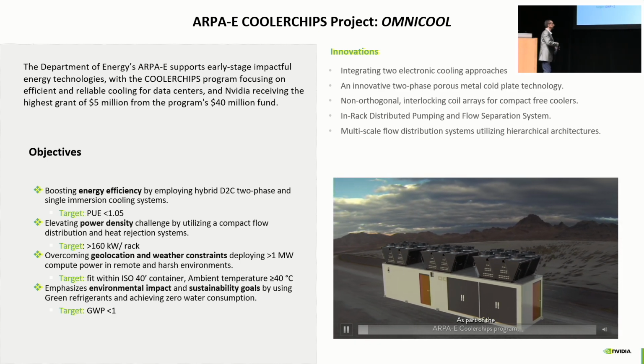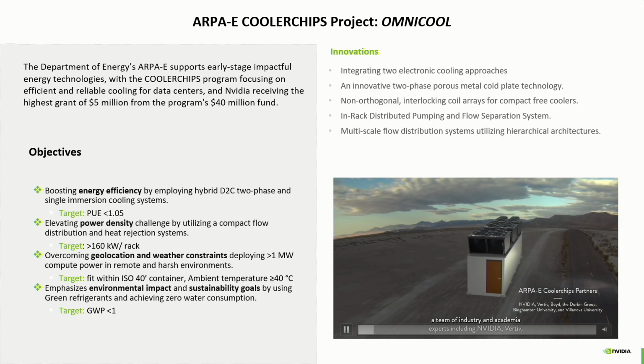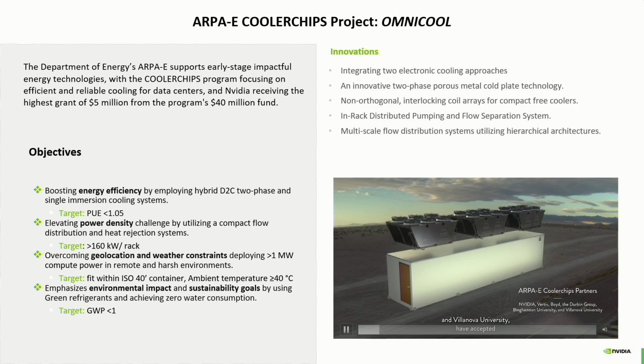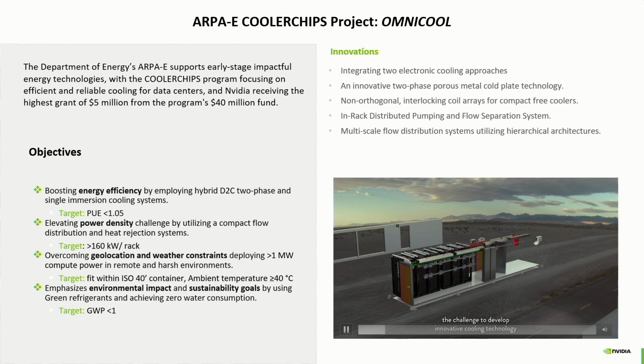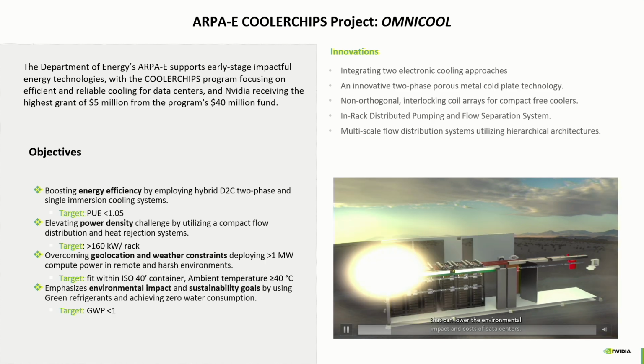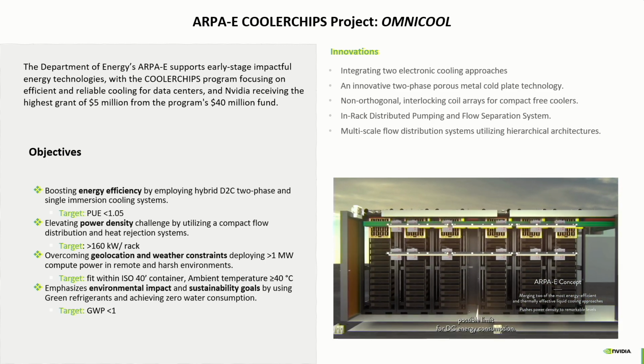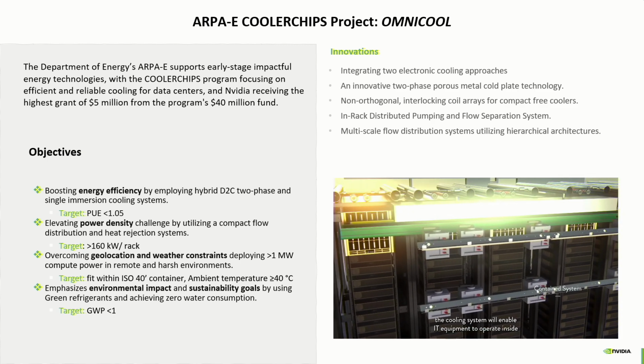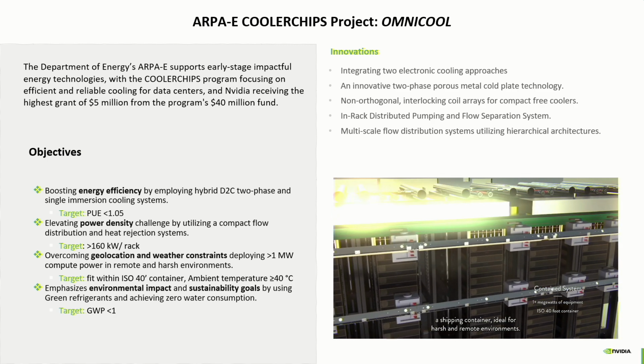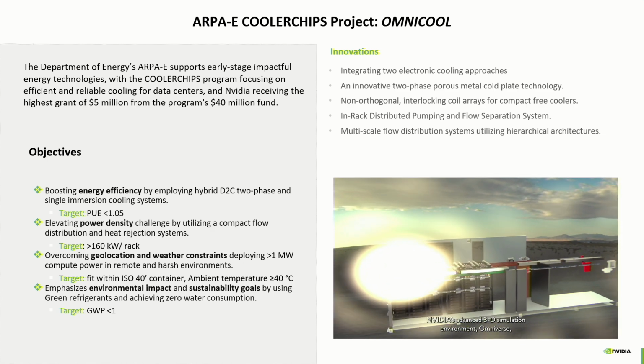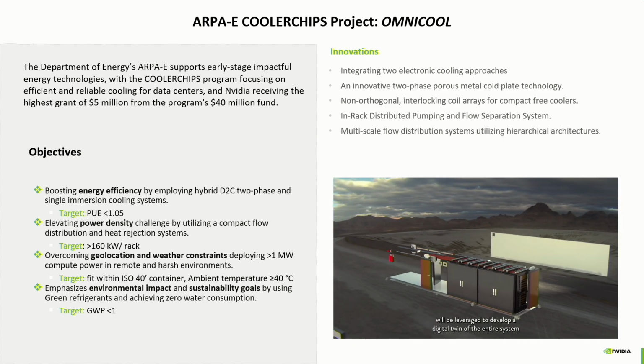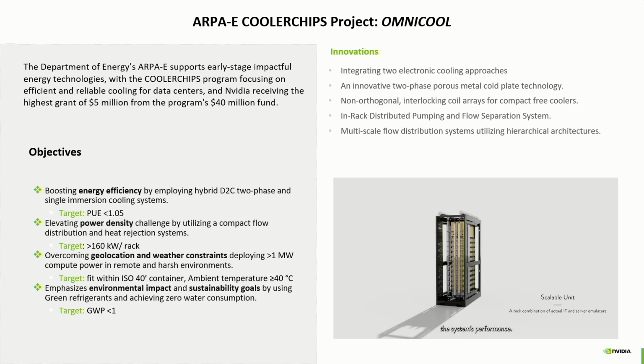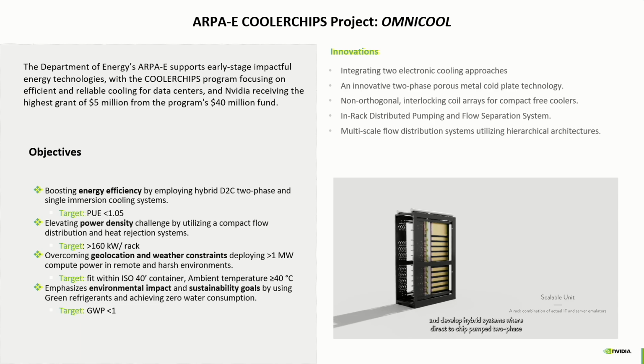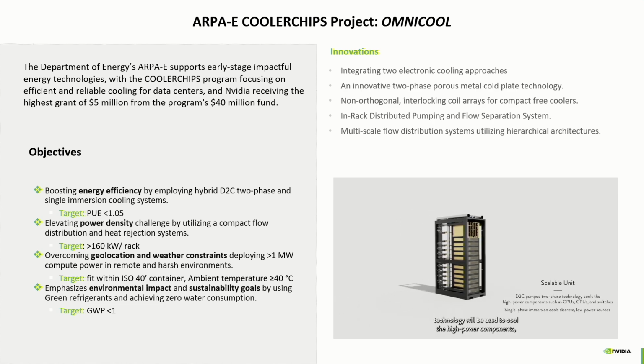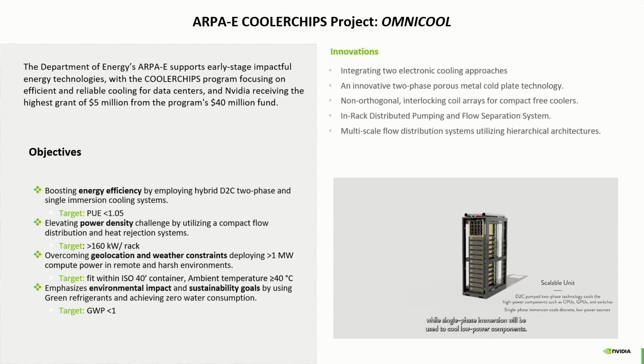As part of the ARPA-E Cooler Chips program, a team of industry and academia experts, including Nvidia, Vertiv, Boyd, the Durbin Group, Binghamton University, and Villanova University, have accepted the challenge to develop innovative cooling technology that can lower the environmental impact and costs of data centers. This cooling technology can achieve the lowest possible limit for DC energy consumption. When deployed, the cooling system will enable IT equipment to operate inside a shipping container, ideal for harsh and remote environments. NVIDIA's advanced 3D simulation environment, Omniverse, will be leveraged to develop a digital twin of the entire system and its advanced cooling technology. A single rack scalable unit will be built to emulate the system's performance. The immersive tray emulators will be utilized to test and develop hybrid systems, where direct-to-chip pumped two-phase technology will be used to cool the high-power components, while single-phase immersion will be used to cool low-power components.